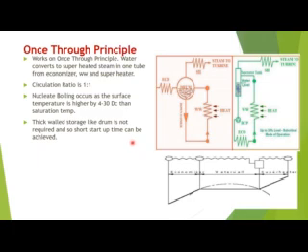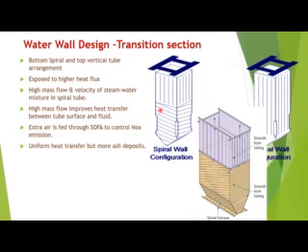Coming to the water wall technology, the bottom segment of the water wall is a spiral segment and the top segment is vertical. Both are connected through a transition segment. The critical state occurs at the transition point itself and is achieved generally after reaching a load of 30 to 40 percent.